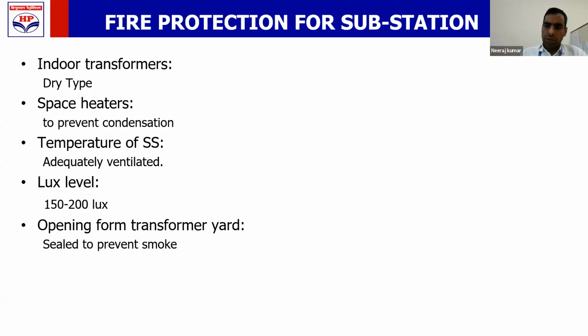To prevent that, you must ensure that all switchgears are provided with space heaters, and those space heaters should be in working condition, especially when your switchgear is in off condition. Some substations are found to be in locations which are at higher temperature than your ambient temperature, especially in boiler areas, in some generating stations also. For those, you should ensure adequate ventilation so that the temperature of the substation does not go substantially higher than your surrounding.